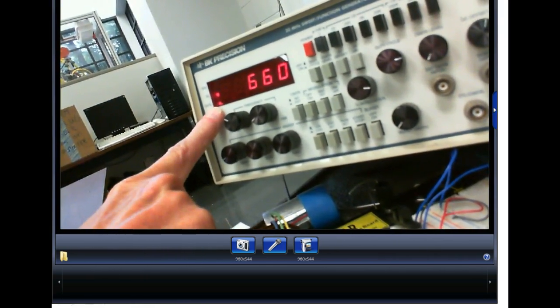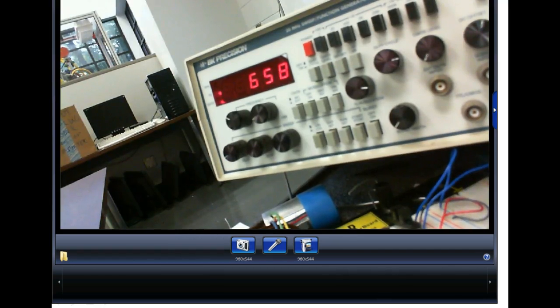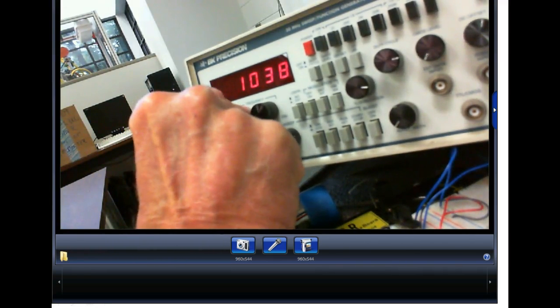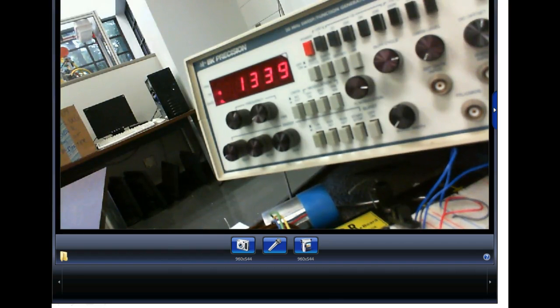Can you see this right here? Frequency counters are slow because it's going through an analog to digital conversion. So we get people trying to set frequencies, and they'll come up here and turn these things, and they don't understand it takes a little while for your frequency counter to do what? Catch up. So people do what they call oscillation, overshoot, undershoot, overshoot.